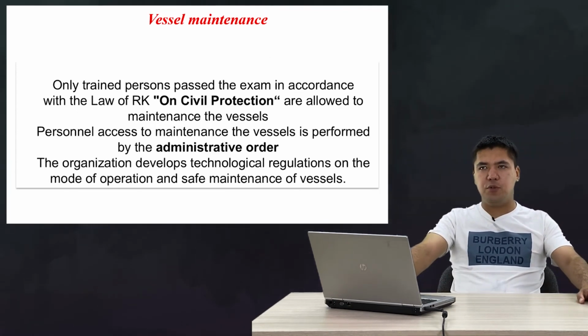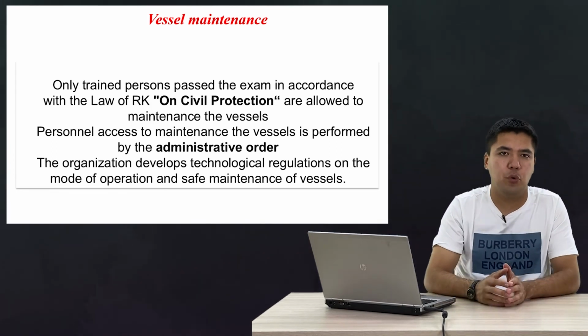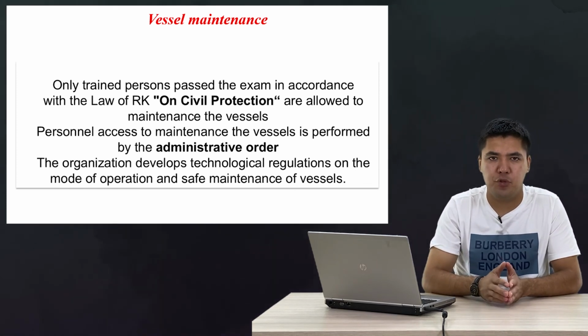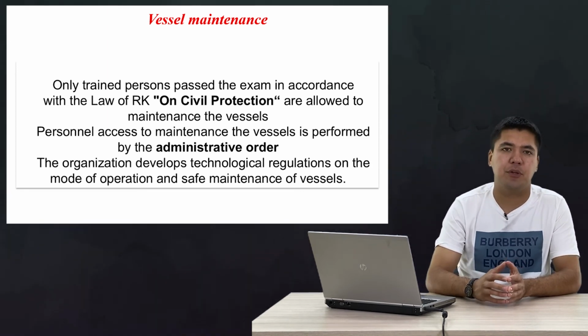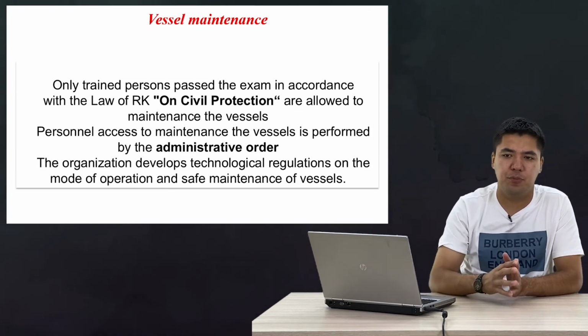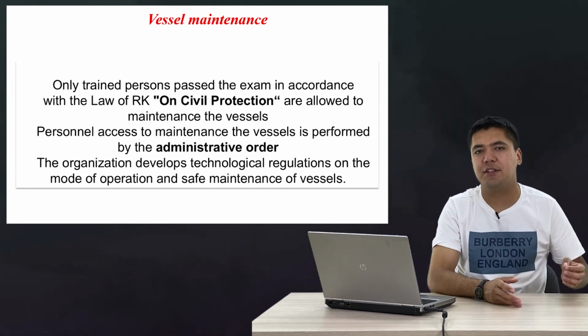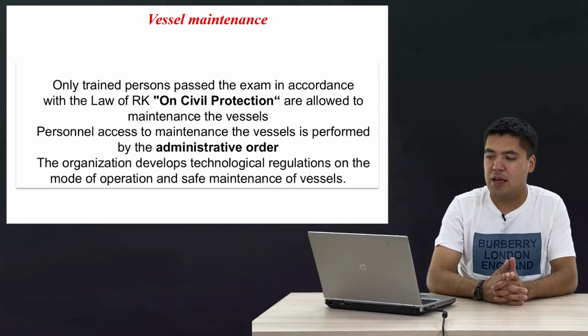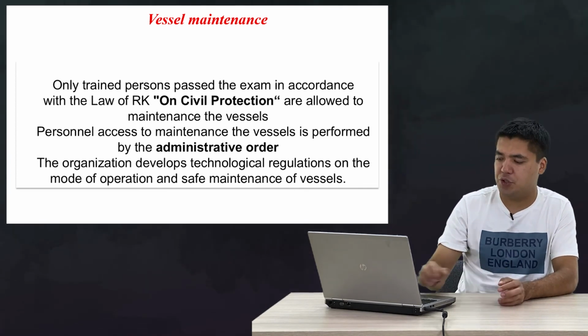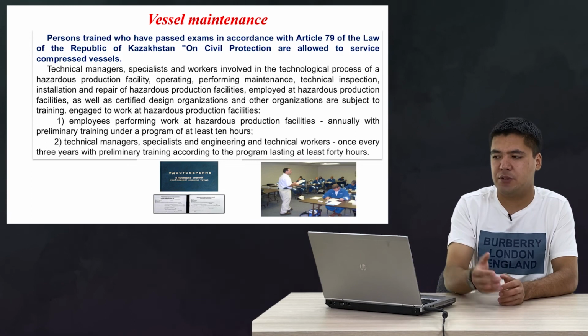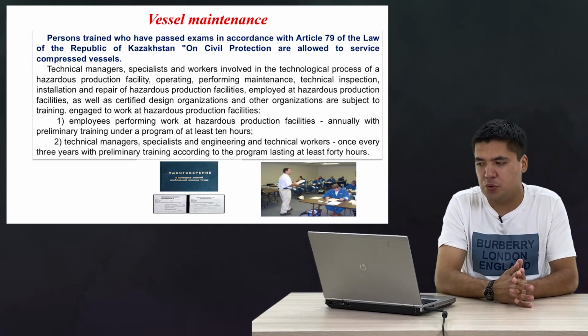And maintenance of the vessel, as I mentioned, is allowed only for qualified personnel who passed this training. Only one person cannot work with a pressure vessel, and a pressure vessel cannot be left alone during operation, because operational personnel must always be staying near the pressure vessels to act in case of any emergencies. And only personnel who have finished the special training according to industrial safety requirements or according to the law on civil protection of the Republic of Kazakhstan can do this work.